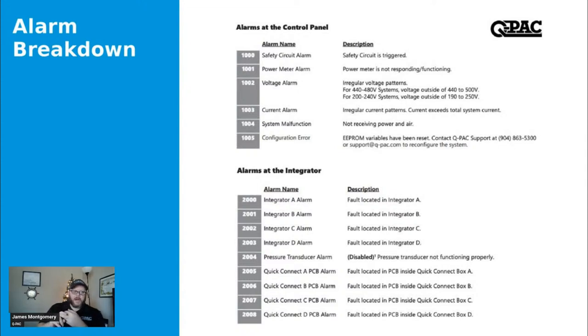The big thing about not having it is, if this unit is going to be connected via BACnet, somebody somewhere has the ability to track the power consumption in the form of wattage. And in order to solve for wattage, you need current and you need incoming power. So when you're not getting that, you're potentially not going to have that data. It may just be an alarm at this point and not essential, but like I said, it's not a shutdown.